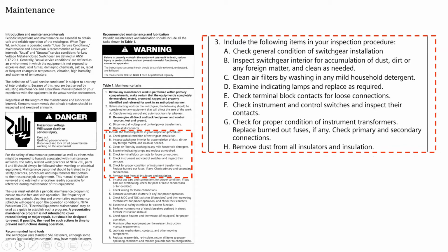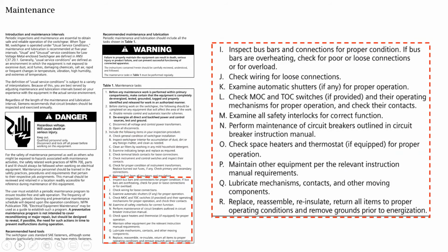Check general condition of switchgear installation. You're looking for dust, dirt, foreign matter, clean the filters, check all your indicating lamps, terminal block contacts for loose connections, and number one biggest failure is going to be loose connections, right? Okay, next. So it goes all the way down to R, right? Perform maintenance of circuit breakers outlined in the circuit breaker installation manual. So really, there's not a whole lot that can go wrong with switchgear, right? It's a big box with bus bars, right? And you got conductors terminated to it, so it's only where the conductors are terminated. Where's your big failure? It's in the breakers, right?